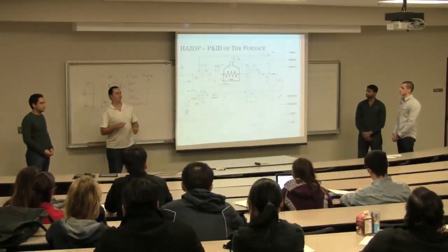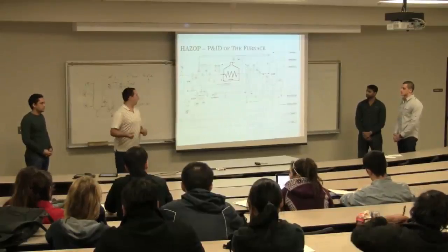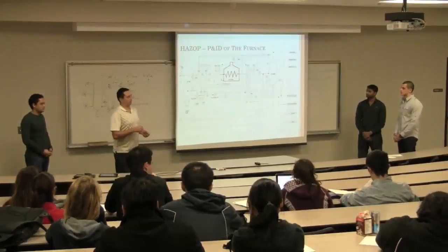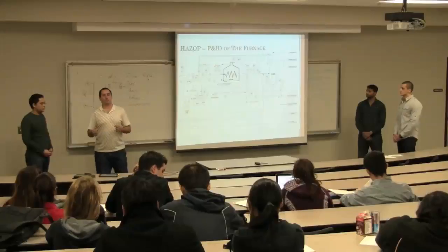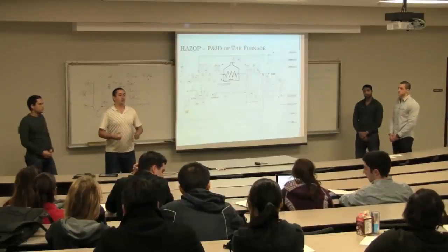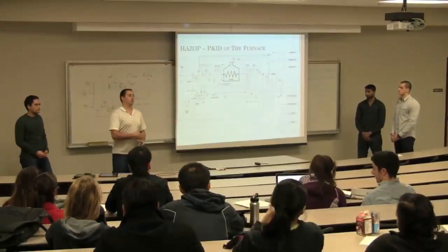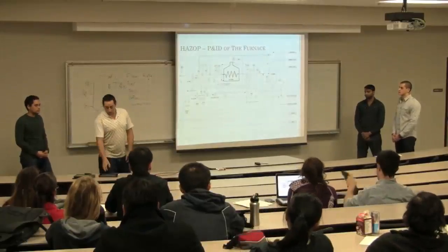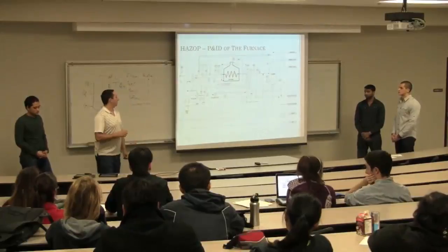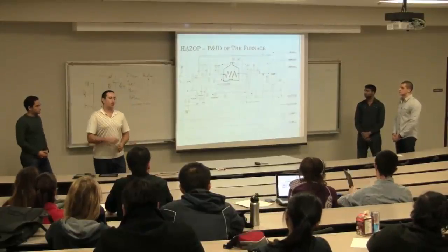For our case, the fuel was mixed with the air before it enters the system. And that could cause a large number of problems, because if it's mixed improperly before it goes into the OTSG, you could just flood the unit or not have enough fuel in the unit for it to even combust. So the parameters that we looked at were flow, pressure, temperature, and composition.